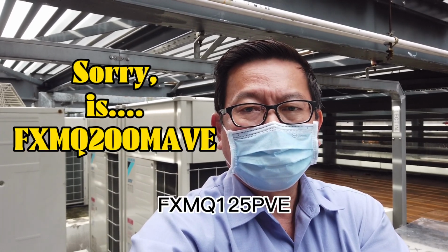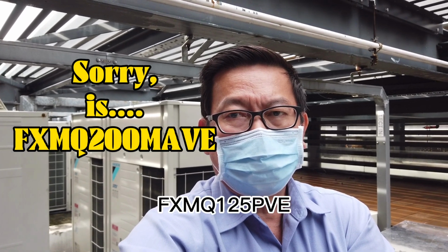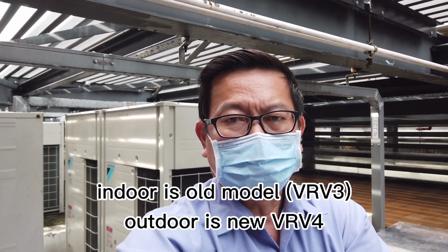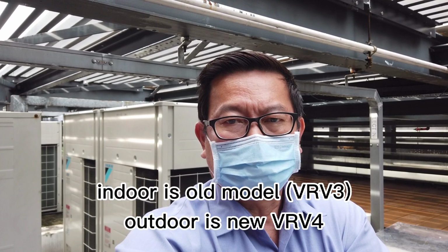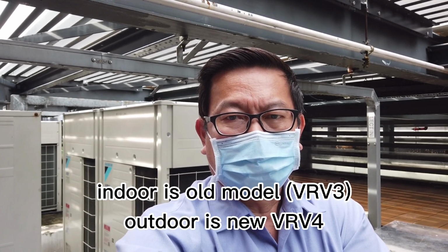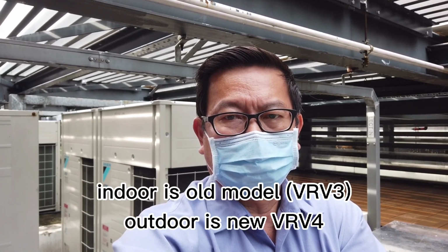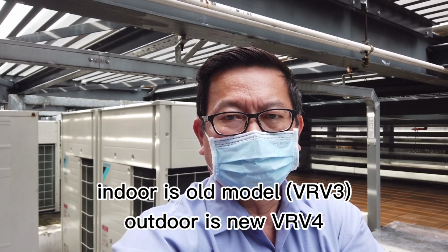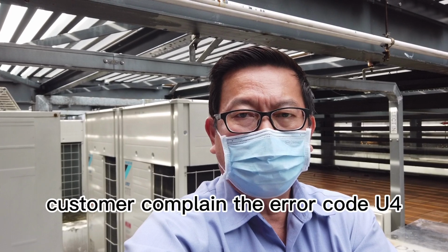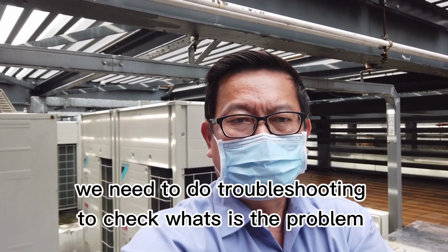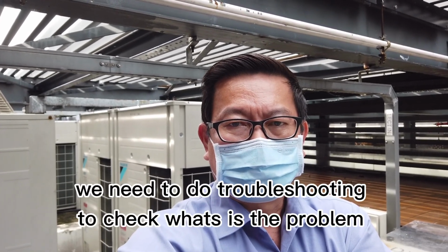Indoor unit is FXMQ125PVE. Indoor is old model, it's a VRV 3 actually. This VRV 4 is just a replacement, the new condensing unit. Customer complained the error code U4. We need to do troubleshooting to check what is the problem.